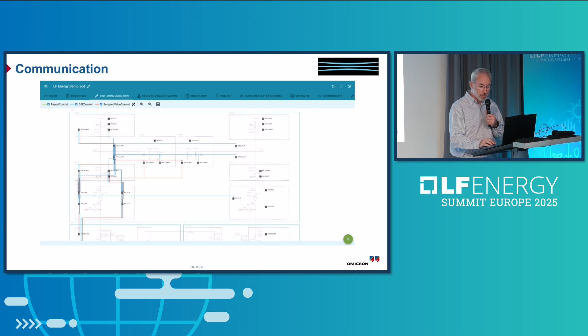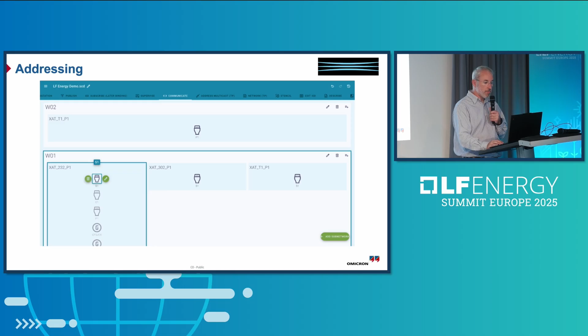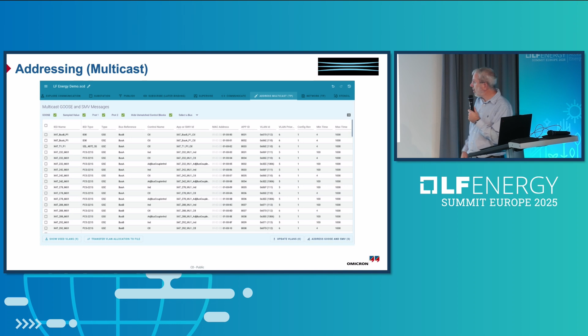After that's done, the addressing can be handled with the communication plugin. The access points can have their IP addresses and so on set. But Transpower didn't stop there - they also created a plugin to automate parts of the addressing: multicast GOOSE and sampled value messages, and VLAN allocations.